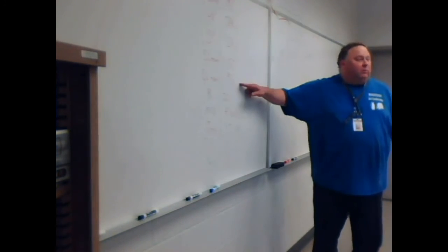If I lose you on these, let me know. Yeah, on that, you see the outside ambient over here is 95, and your liquid line is 95. So we're doing all we can do, right? How could this be 94?